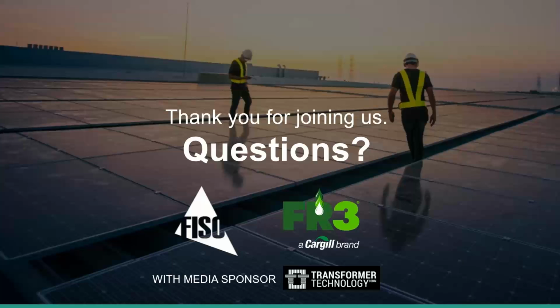Well, the viscosity of FR3 is higher than mineral oil, and we have seen in our experience that viscosity is not the only driver, the property to look at when we are talking about heat transfer. So we need to take into account viscosity, but also heat transfer and specific heat of the fluid we are talking about. And as specific heat and heat transfer have higher values on FR3, this compensates somehow the higher viscosity of the fluid. I can say that in distribution transformers, we are seeing an increase in the top oil temperature around 3-4 degrees, which is still pretty far from the limits for that value on the standards.